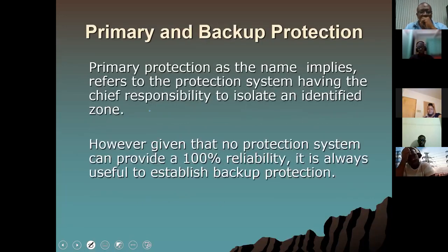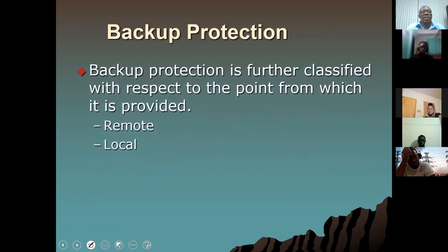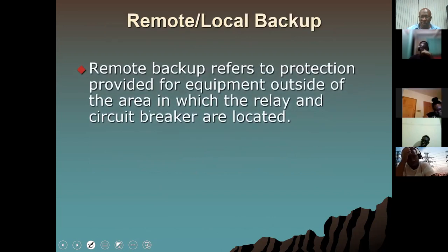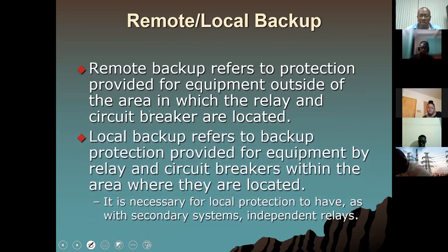So with that said, the backup protection, either being remote or local, simply means that for the local, it is occurring within the same substation. For remote, the backup is being provided outside of the substation. Clear? Nice and easy. So backup is either remote or local. All right? So if it is outside the substation, you're outside the area where the circuit breaker and relay are located. And if it's local, it's within the area where they are located, or in other words, within the same substation.